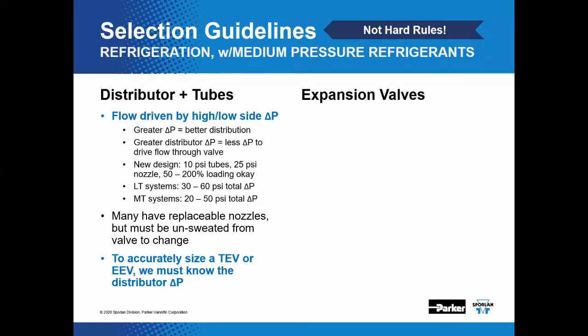Now, in the distributor tube assembly, flow is driven by our high to low side pressure difference, delta P, if you will. In general, greater delta P means more even distribution to the coil circuits. In a new system design, Sporlan guidelines call for 10 psi drop through the tubes and 25 psi drop across the nozzle. Those guidelines also tell us that 50 to 200%, as calculated by our selection program software, is acceptable. For our discussion, we're going to try to stay within 30 to 60 psi total delta P for low temp systems and 20 to 50 psi for medium temp systems.